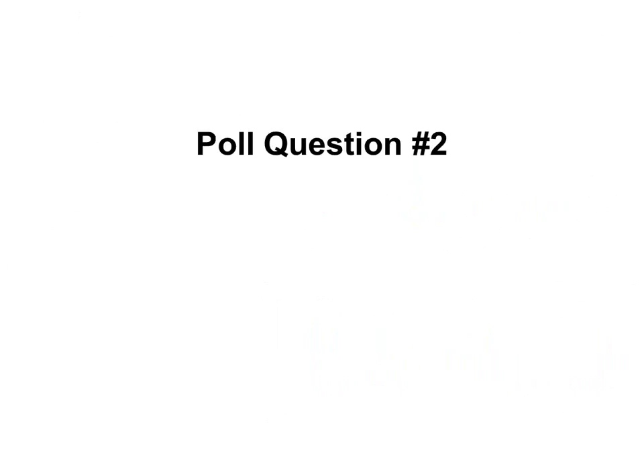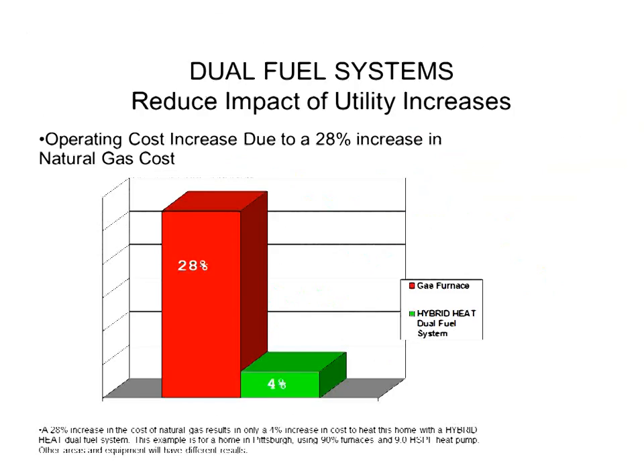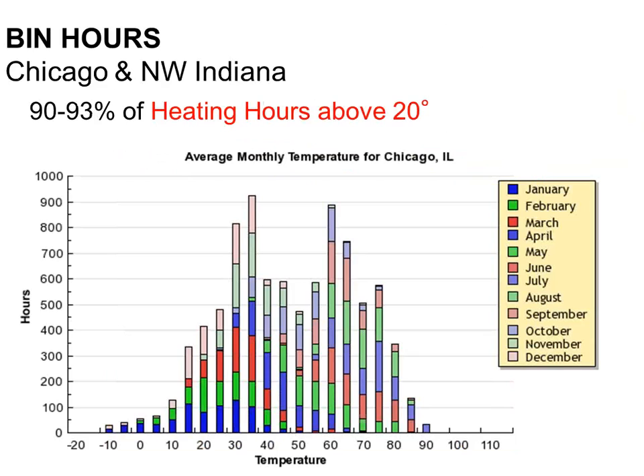All right, the previous charts I showed you were on the heating scenario, really. The one I'm showing you now is a cooling argument, if you will: generally speaking, the vast majority of your cooling hours are not at peak either. So I don't really care about what happens at peak design day heating or design day cooling. I mean, I care because I have to be able to cover the load on those days, but I don't care from an efficiency standpoint what happens when it's 95 degrees or 0 degrees outside. Efficiency is irrelevant because it happens so infrequently. I want to know how efficient this system is going to be between 20 and 80 degrees outside.